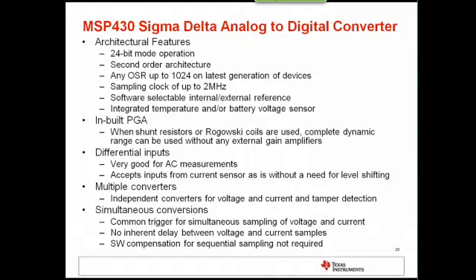In the MSP430, the Sigma Delta ADCs operate in 24-bit mode with a second-order architecture. Basically, you have a modulator which modulates the analog input using the reference voltage and the modulation clock. This produces a bit stream that's fed to the digital filter, and the digital filter averages a certain amount of these bits to produce one effective sample. The amount averaged to produce one effective sample is called the oversampling ratio.